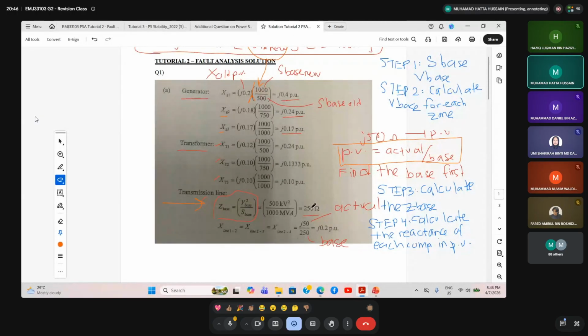But remember one thing, when I taught all of you last semester, you need to memorize the formula. Z base equal to V base squared divided by S base, which means that 500 kV squared divided by 1000 MVA equal to 250 ohm. This formula, I hope that all my students can remember. This is very, very important because in order to find the per unit value, you need to know the base. You need to know the base formula. Okay, then from here, this is the actual, this one is the base. So we have the value in per unit. Okay, this is the basic concept in per unit.